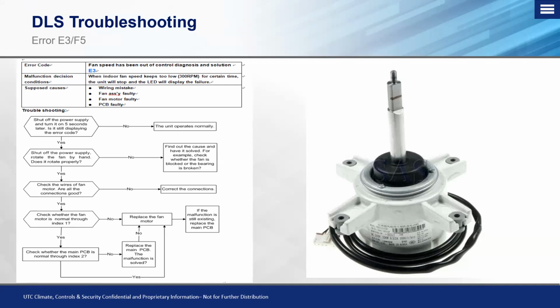the correct code. Just like we had on our first tech tip with our E1, of course, you always want to reference the flow chart that comes with the service manual. And again, I'll state on here, this is a great way to get you in the right direction for some things to look at to troubleshoot this specific code. However, be very wary when following the flow chart, because as I stated before, you can end up replacing multiple boards and mechanical components, and your issue will still be there. It's just essentially a guide through that code to help you start looking at and checking specific things. And of course, if you feel uncomfortable with anything, you can always reach out and call me directly, and I can help walk you through troubleshooting specific parts of that system.